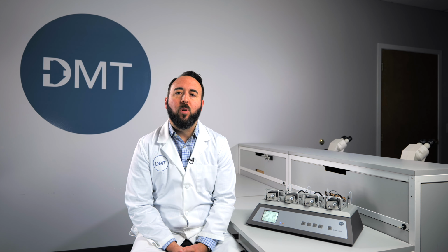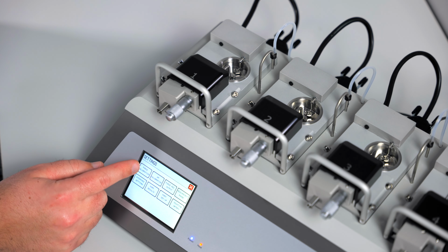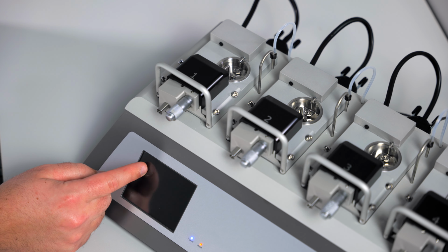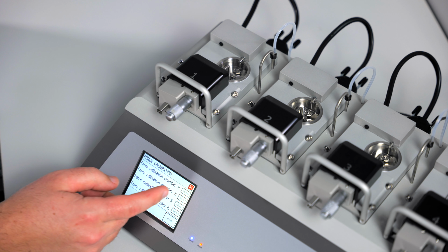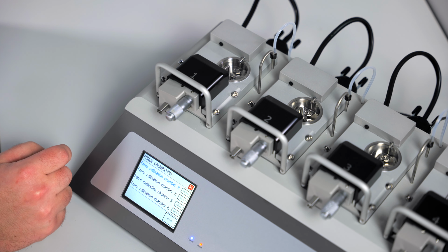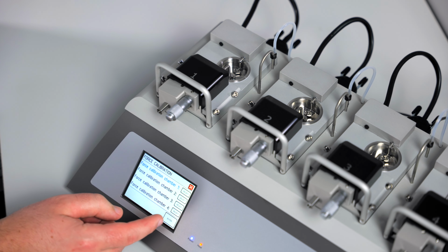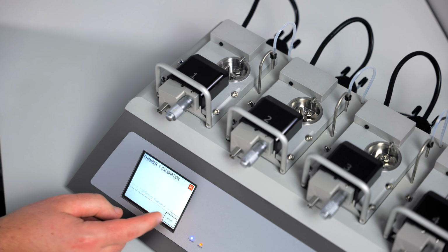In order to calibrate, you will need to access the force calibration menu. This can be found in the settings and then force calibration. We will highlight channel 1 as that is where we will be doing our calibration. Press enter to take you into the menu. This will show you a 6-step process. However, there are only a few steps that you are actually doing anything.